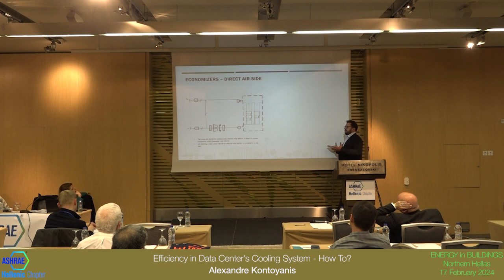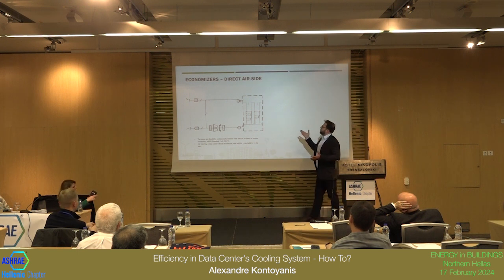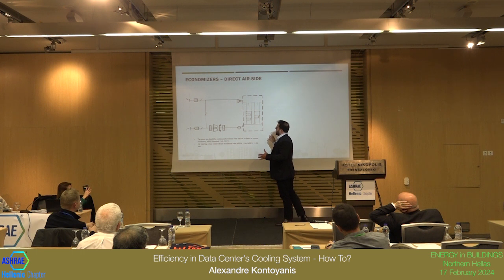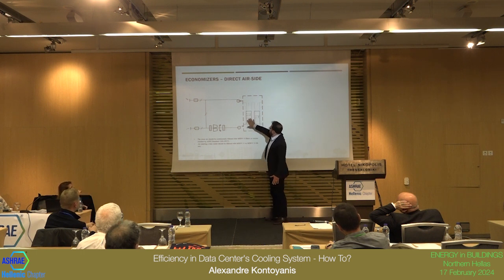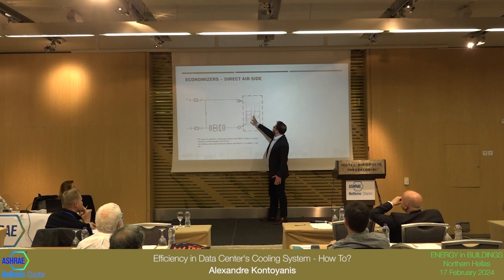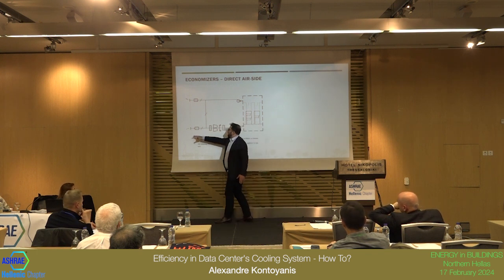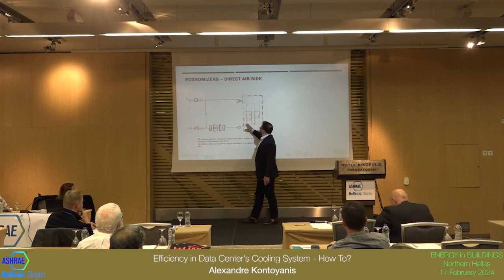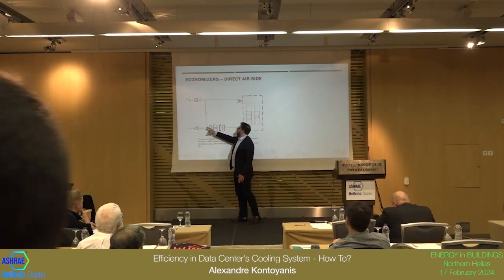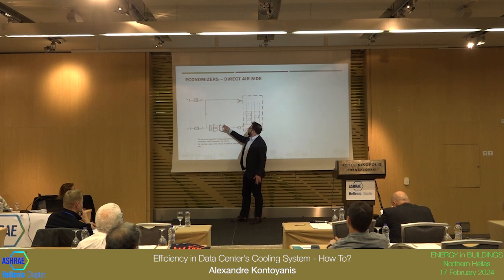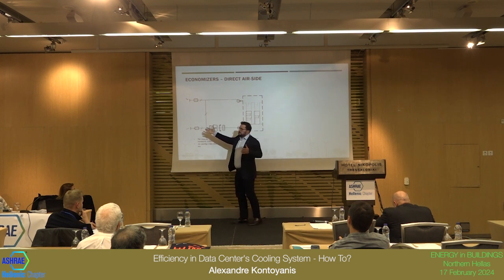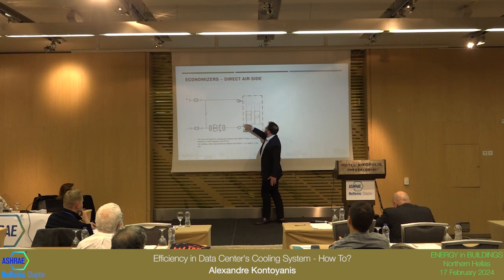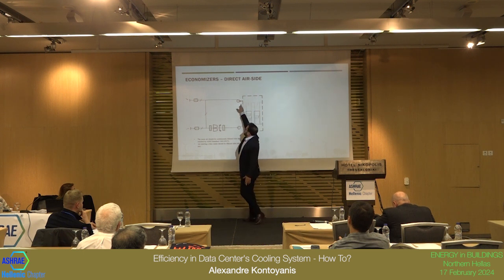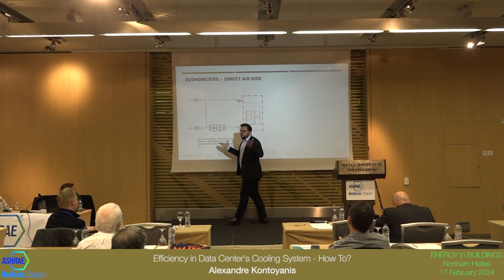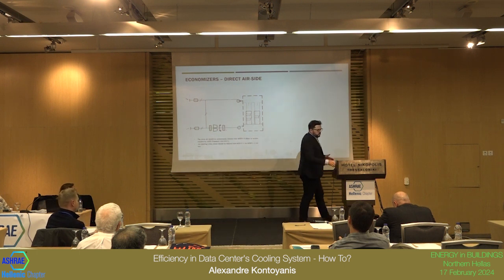Let's go with two types of economizers here. This is a direct airside economizer. It's the simplest we have. We have the data center here, the racks, cold aisle, hot aisle, and you have the air coming straight from the outside to the inside. Of course, you have silencers, dampers, filters, humidifiers. You have a DX coil here as a backup. You never know when it's hotter than you expect outside. You have the fans here, and the air goes to the racks and goes back to the outside air. Very simple. From an engineer's point of view, a very simple system.